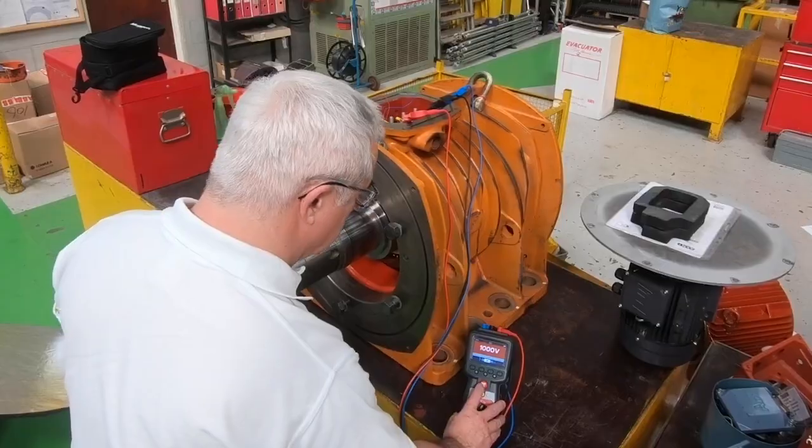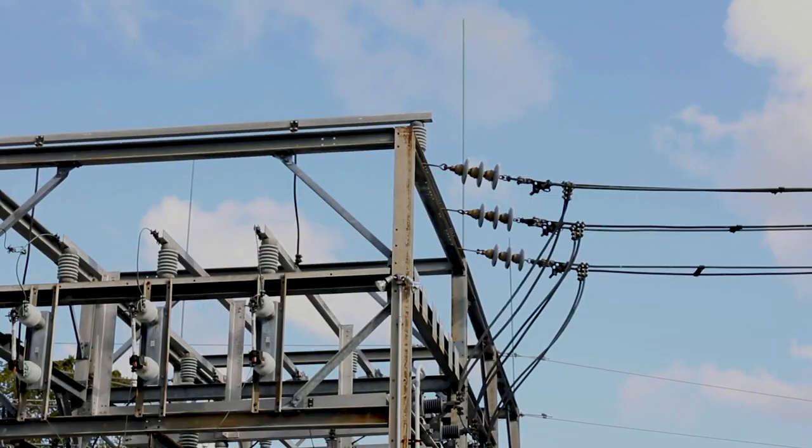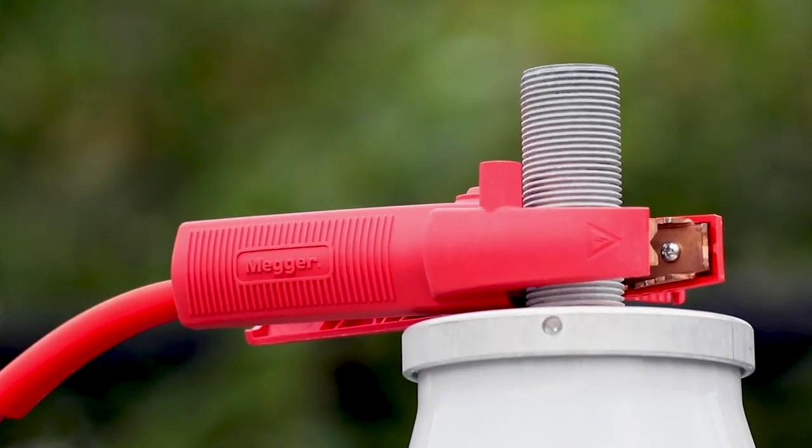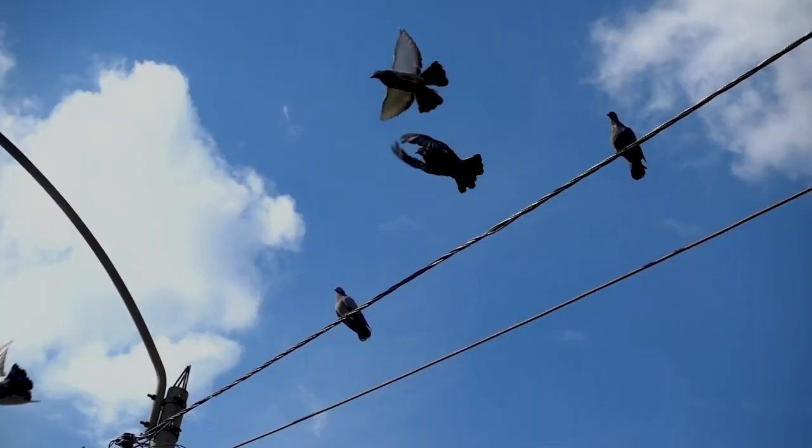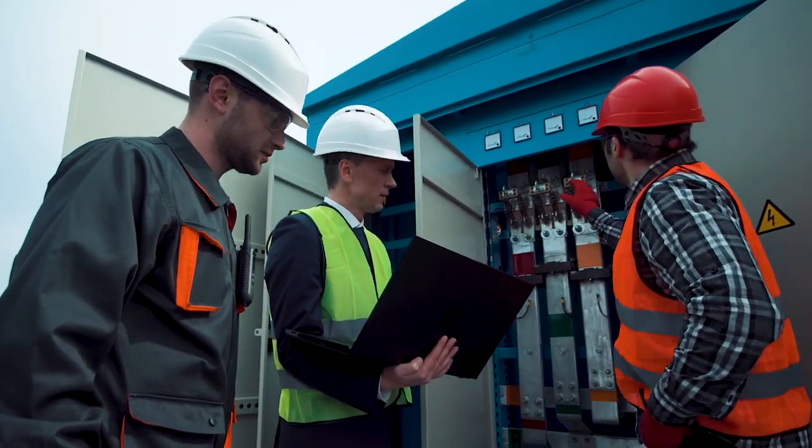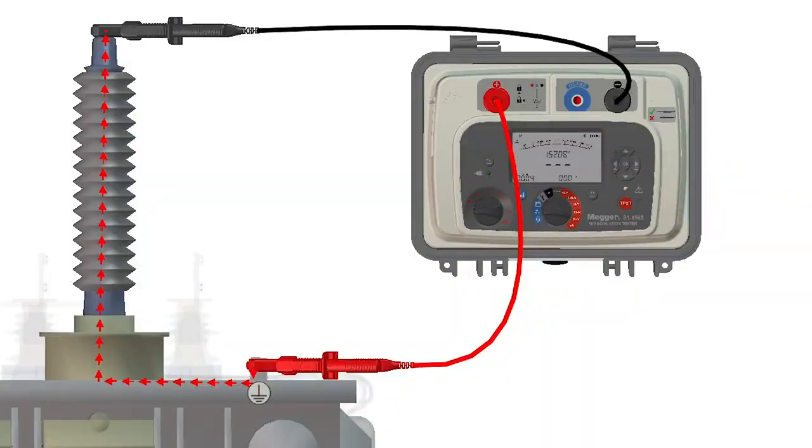Checking the insulation integrity of assets such as cables, motors, or bushings requires tests to be conducted at high voltages in order to measure minute currents. If an asset surface is contaminated with dirt or moisture, it will produce a surface leakage current that will distort results.